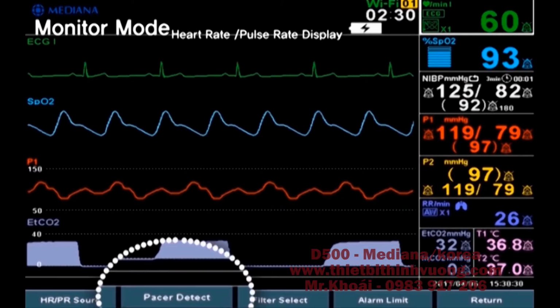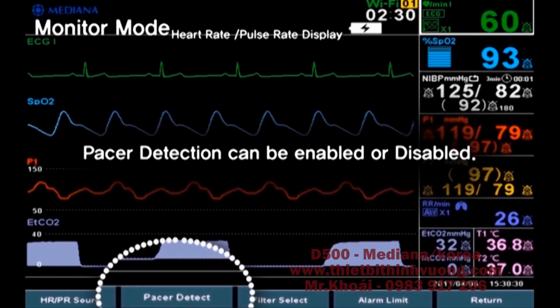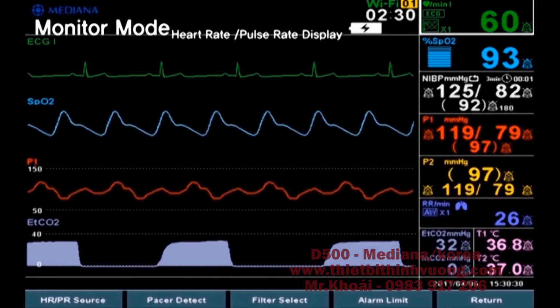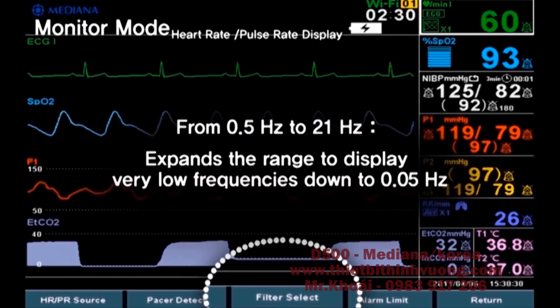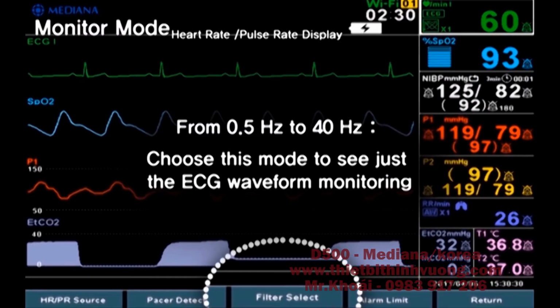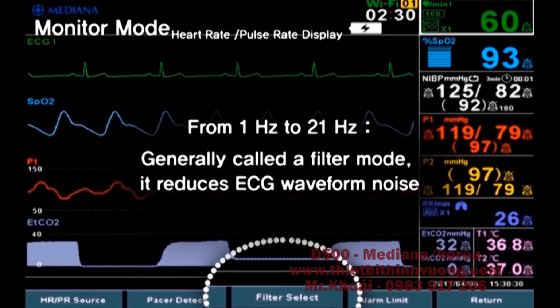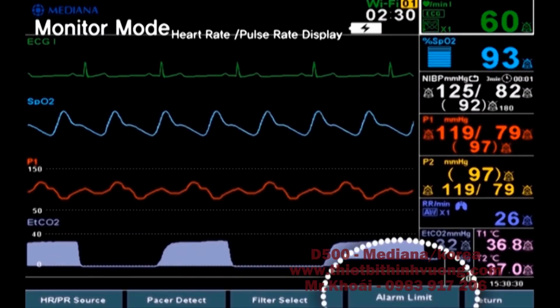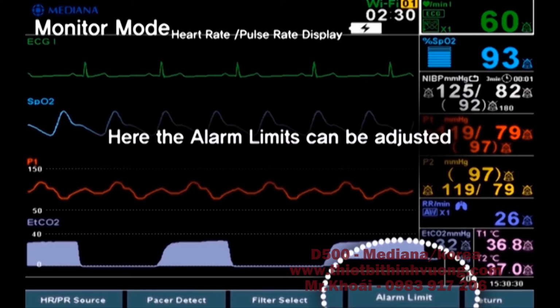Number 2, pacer detect. Pacer detection can be enabled or disabled. Number 3, filter select. Let's check the differences of filter select ranges. From 0.5 Hz to 21 Hz. Expands the range to display very low frequencies down to 0.05 Hz. From 0.5 Hz to 40 Hz, choose this mode to see just the ECG waveform monitoring. From 1 Hz to 21 Hz, generally called a filter mode, it reduces ECG waveform noise. Number 4, alarm limit. Here the alarm limits can be adjusted.